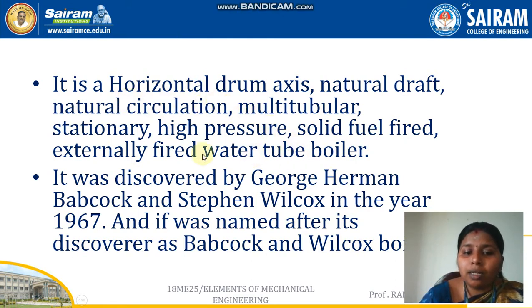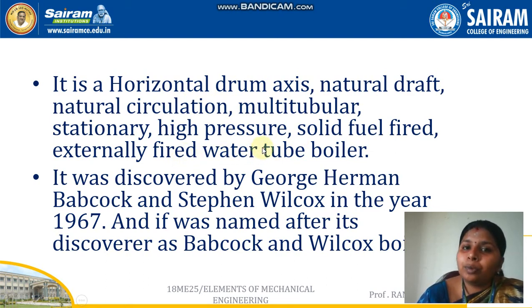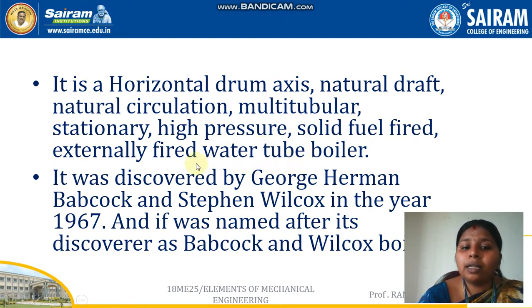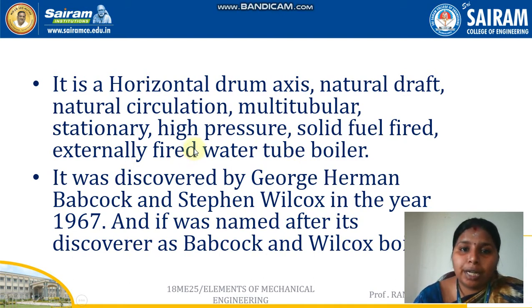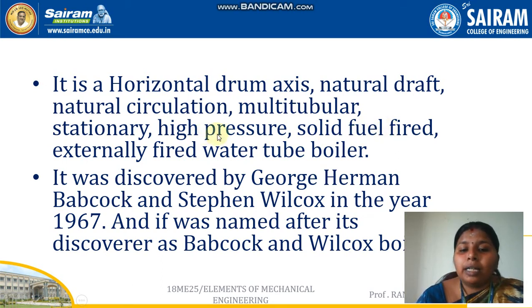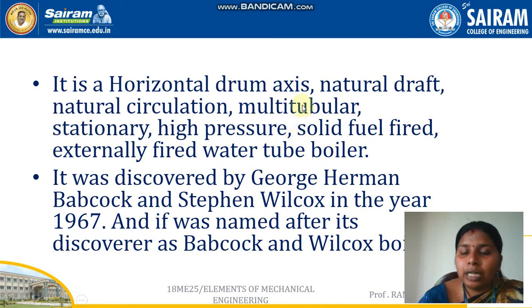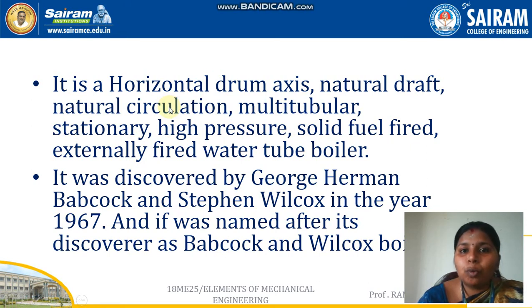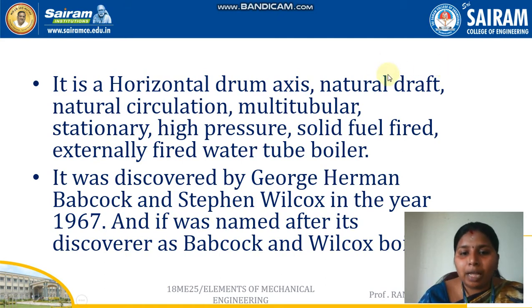As we saw in the previous video, there are two types of boilers: water tube and fire tube. The Babcock is a water tube boiler. It is externally fired, meaning the furnace is kept outside the boiler drum. The fuel used is solid fuel, it can handle high pressure, it is a stationary type, multi-tubular containing many tubes, and uses natural circulation — no pump is required to force water into the drum.